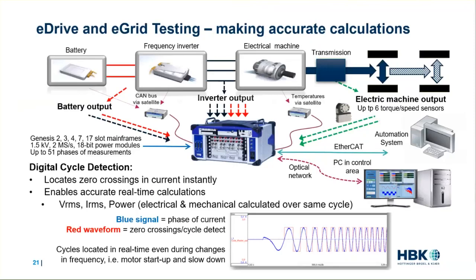And that's going to eliminate the common efficiency error of greater than 1, which often happens due to misalignment of the calculation in electric drivetrain measurements. In fact, this technique enables calculations to be performed even when the frequency of the phase of current changes due to dynamic load changes. For example, motor startup, slow down, going up a hill, or down a hill.